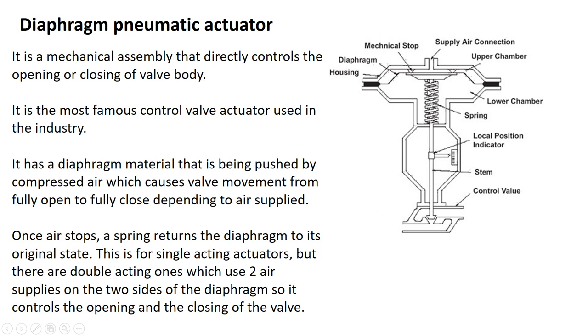When you remove air, the spring returns the control valve to fully open or fully closed depending on the system. This is called single acting because there is only one air supply. There is also double acting, which has a second air input to determine the position from both sides.